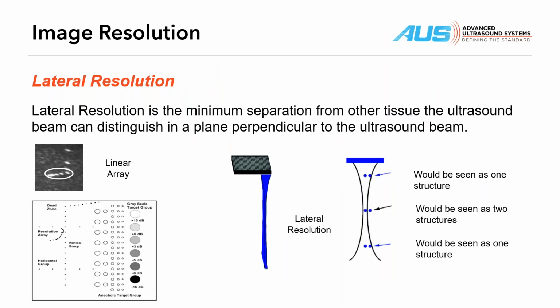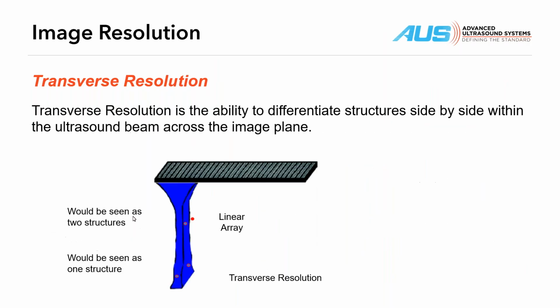And just a side note here, the resolution array right here that's set up on what we recommend is the 539 Phantom, the model 539. This resolution array allows you to capture images that help you evaluate axial and lateral resolution. So you have axial going top to bottom and lateral going left to right, with a curve representing both, or detail resolution.